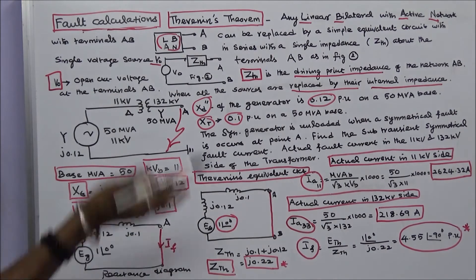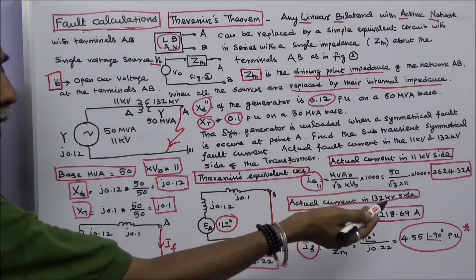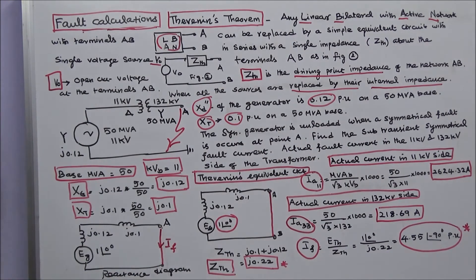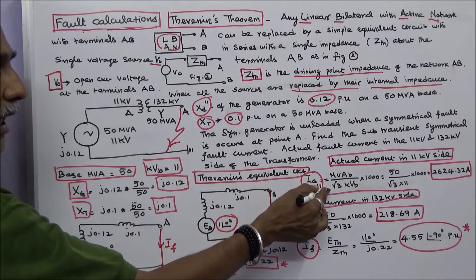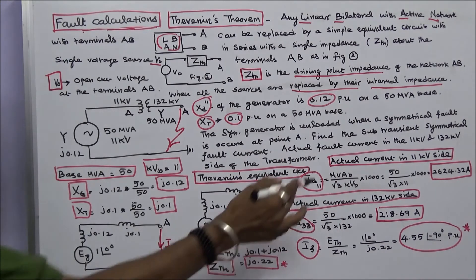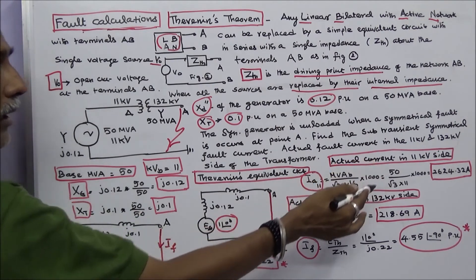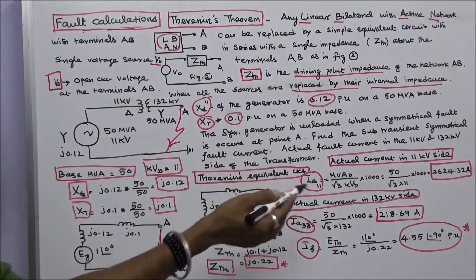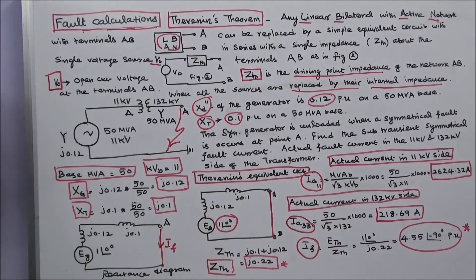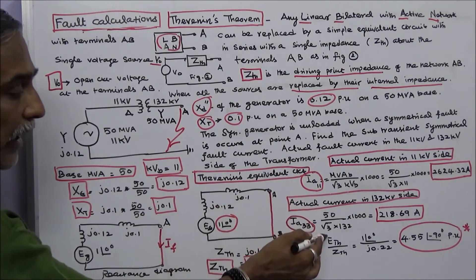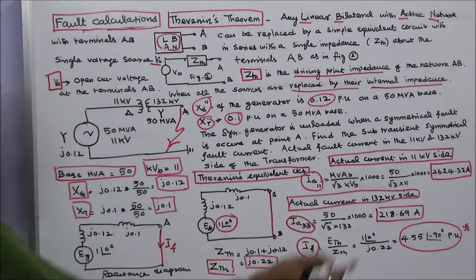The next step is to calculate actual current in the 11 kV side and actual current in the 132 kV side. Actual current in the 11 kV side is equal to MVA base divided by root 3 into kV base into 1000. So 50 by root 3 into 11 into 1000, that is equal to 2624.32 Amps. Similarly, in the 132 kV side, actual current is 50 by root 3 into 132 into 1000, that is equal to 218.69 Amps.